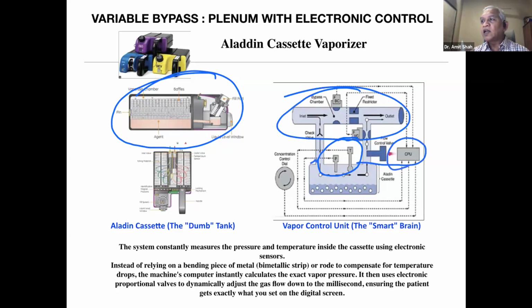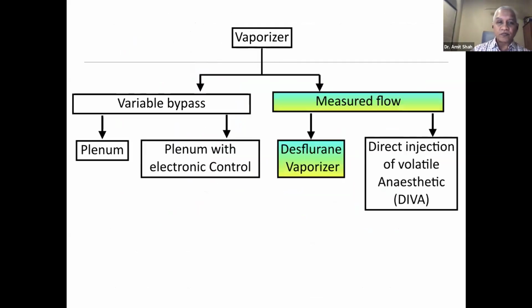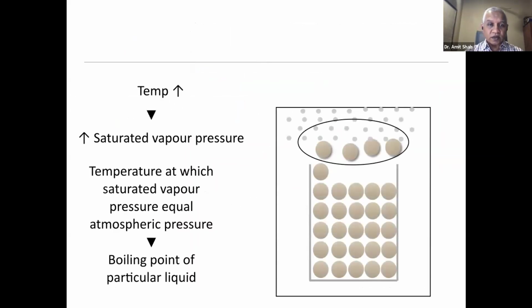So it is basically an electronic vaporizer which has temperature and pressure sensors inside the chamber, which inform the computer, which alters the bypass flow. Okay, so that's a plenum electronic control vaporizer, which is used in the cassette. Now let us look at the desflurane vaporizer.